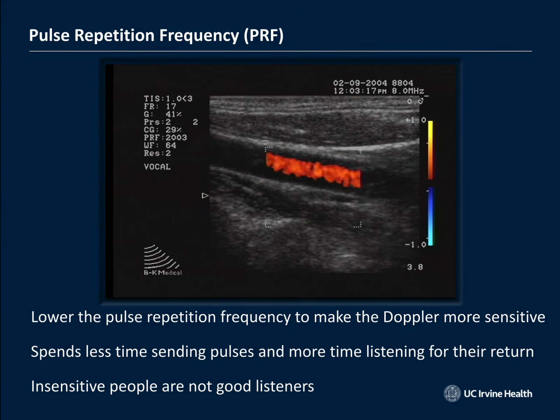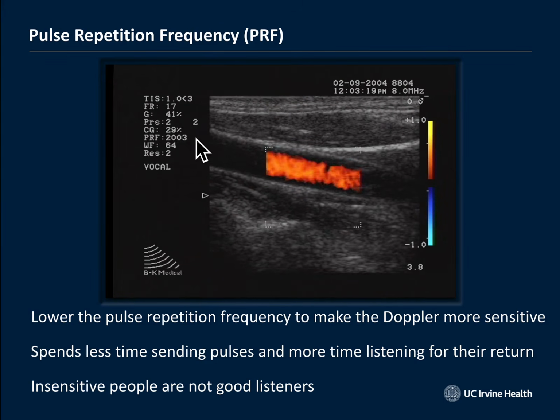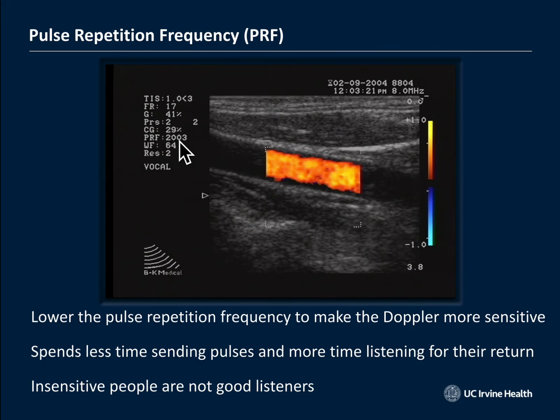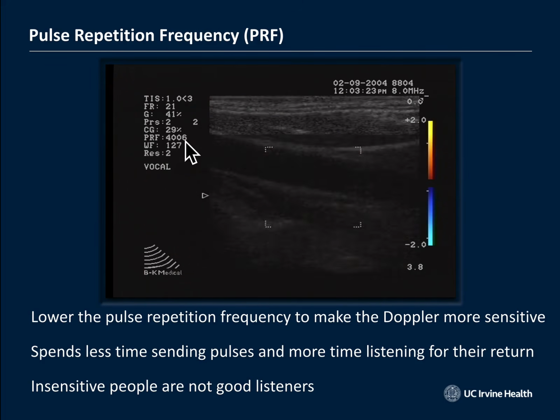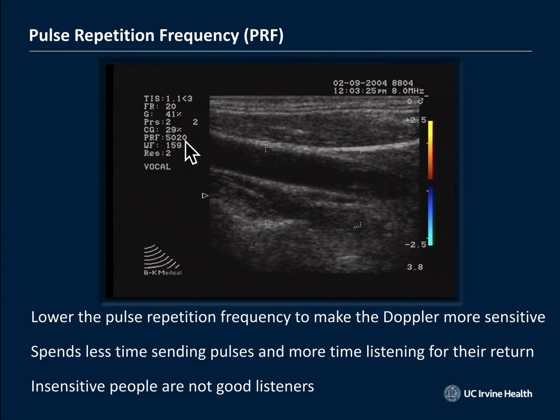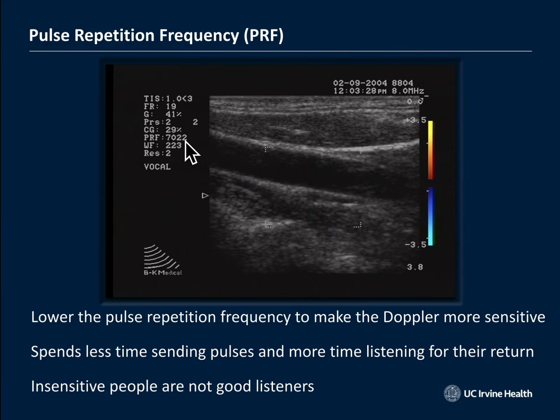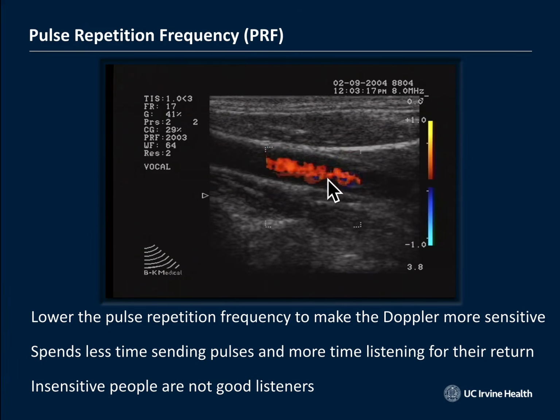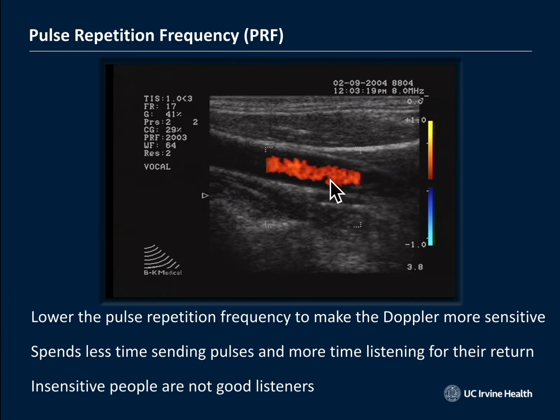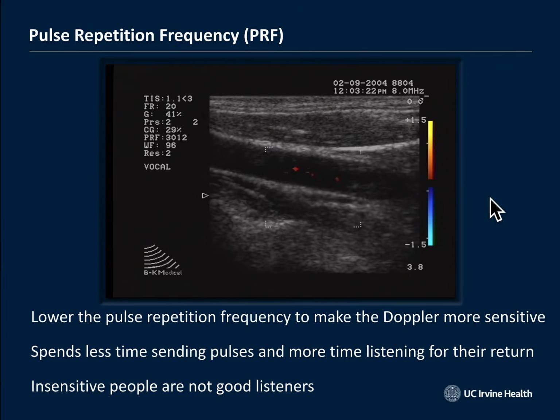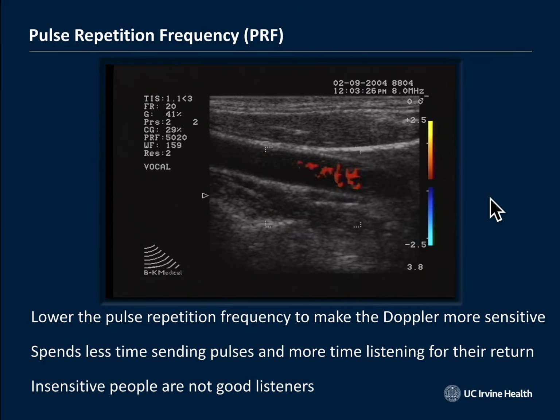And so you can see here on this view, we've got the PRF at 2,000. Now it's at 3,000. It's 4,000, 5,000, 7,000, and as you get up to 9,000, you don't see as much flow anymore. And then back down to 2,000, we see a lot of flow here. So that's one way that you can adjust the sensitivity, with the PRF. I usually start there.